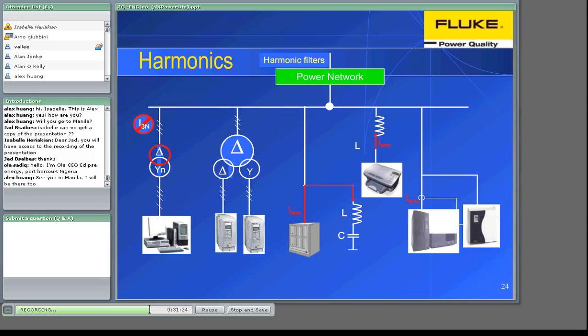Anyway, in some installations, the harmonic content is less predictable. A convenient solution is active filters or intelligent filters. Active filters, sometimes called AHC, active harmonic conditioners, continuously monitor the harmonic current demanded by the load and counteract the harmonic by injecting equal and opposite signals into the supply to cancel the offending waveform or signals.